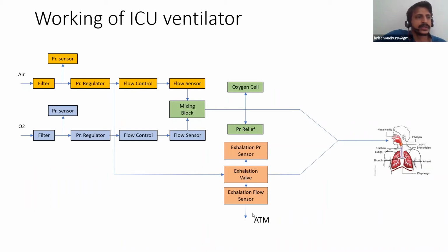And the flow sensor here basically measures the amount of air that goes out, and the exhalation pressure sensor also measures the pressure at which the patient is breathing out.